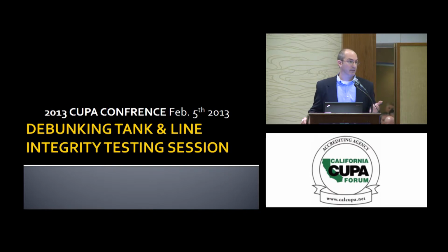And again, for a line test, a certified technician has to go to the site to conduct the test, and we'll also examine the condition of the dispensers and the sumps and other things while at the site. The electronic line leak detection can run automatically from the console, or can be run manually from a person at the console or dialing in remotely.